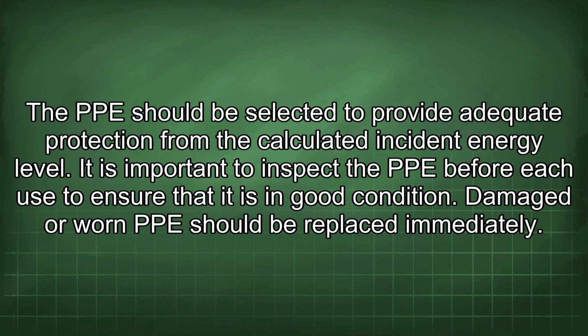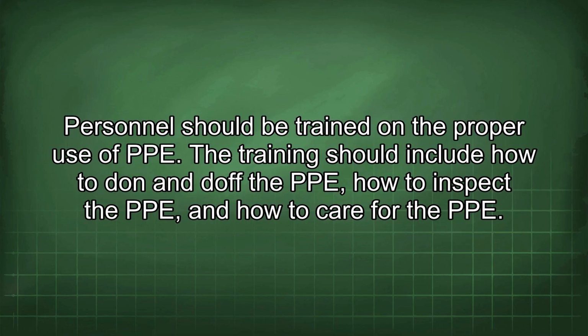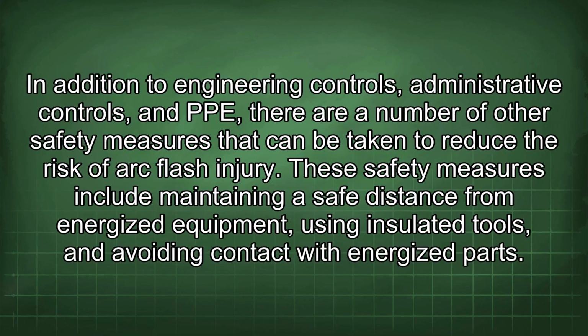The PPE should be selected to provide adequate protection from the calculated incident energy level. It is important to inspect the PPE before each use to ensure that it is in good condition. Damaged or worn PPE should be replaced immediately. Personnel should be trained on the proper use of PPE. The training should include how to don and doff the PPE, how to inspect the PPE, and how to care for the PPE. In addition to engineering controls, administrative controls, and PPE, there are a number of other safety measures that can be taken to reduce the risk of arc flash injury.